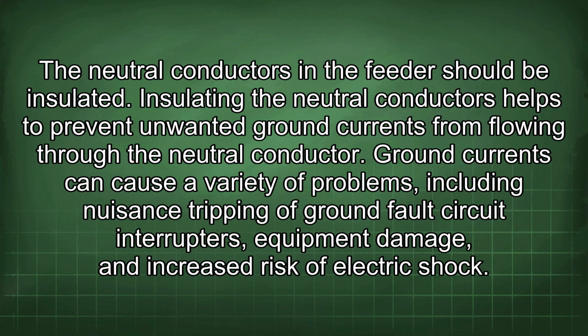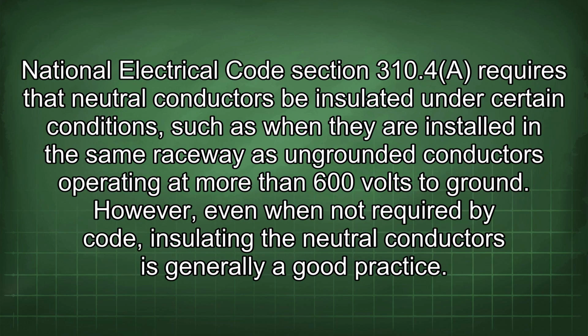The neutral conductors in the feeder should be insulated. Insulating the neutral conductors helps to prevent unwanted ground currents from flowing through the neutral conductor. Ground currents can cause a variety of problems, including nuisance tripping of ground fault circuit interrupters, equipment damage, and an increased risk of electric shock. National Electrical Code Section 310.4 requires that neutral conductors be insulated under certain conditions, such as when they are installed in the same raceway as ungrounded conductors operating at more than 600 volts to ground. However, even when not required by code, insulating the neutral conductors is generally a good practice.